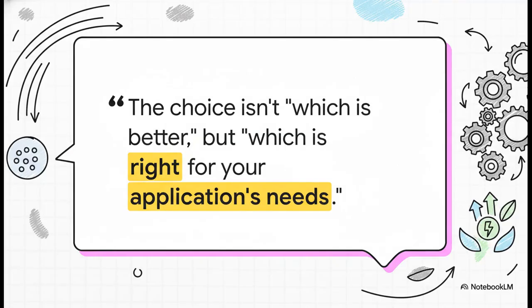At the end of the day, it all comes down to this: the question is never which one is better, it's always what does my application actually need. If you just need a smooth start for a motor that's going to run at one speed, a soft starter is the perfect, most cost-effective tool for the job. But if you need precise, continuous control over speed, and you want to squeeze every last drop of energy efficiency out of your system, the VFD is really your only option.